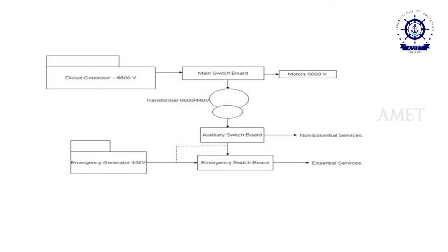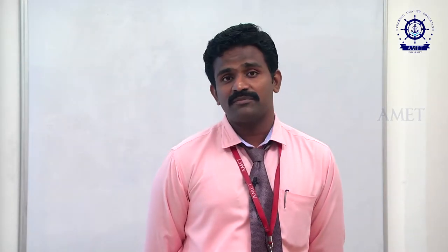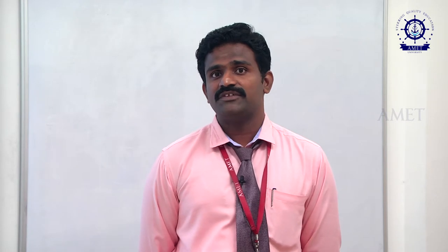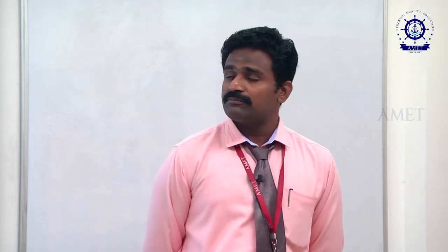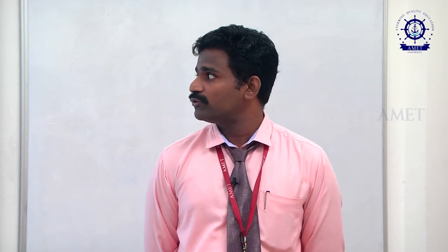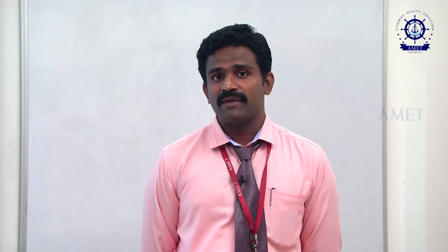From this picture, we can see a simple block diagram showing the interrelation between the main generator and the emergency generator. The main generator gets its supply from diesel and produces 6.6 kV. That supply goes to the main switchboard. From the main switchboard, a transformer steps down the voltage and sends it to the auxiliary switchboard for non-essential services.